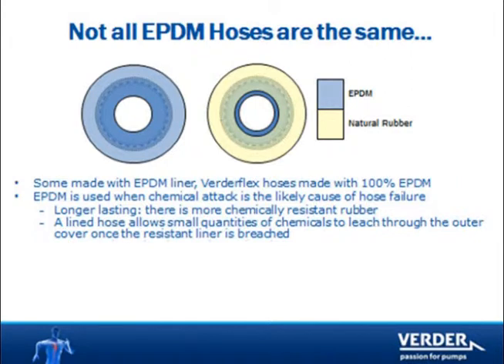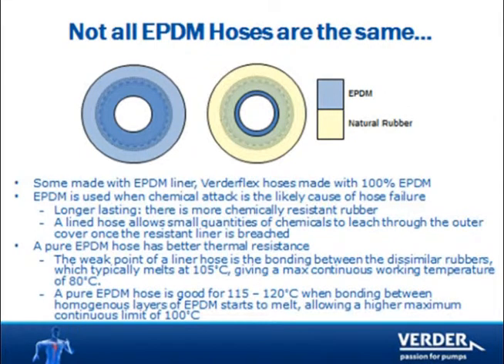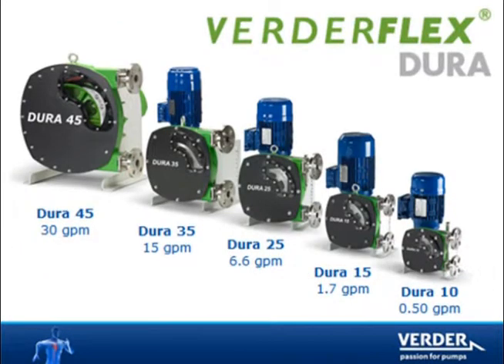Verderflex EPDM hoses are entirely homogeneous. Other EPDM hoses use a thin liner of EPDM bonded to natural rubber. There are two advantages here. First, EPDM handles higher temperature than natural rubber, so our EPDM hose can pump temperatures up to and above 212 degrees Fahrenheit. Second, liner hoses typically fail when the liner strips out of the hose. We have no liner, affording maximum hose life.